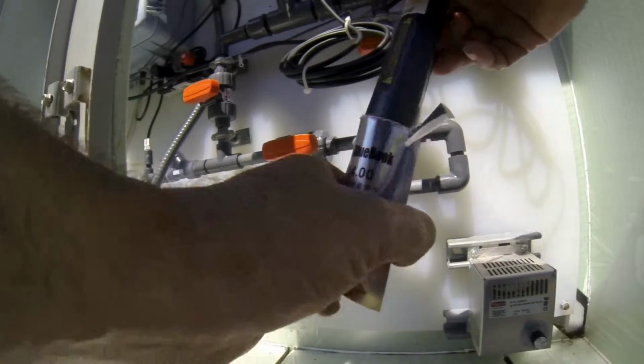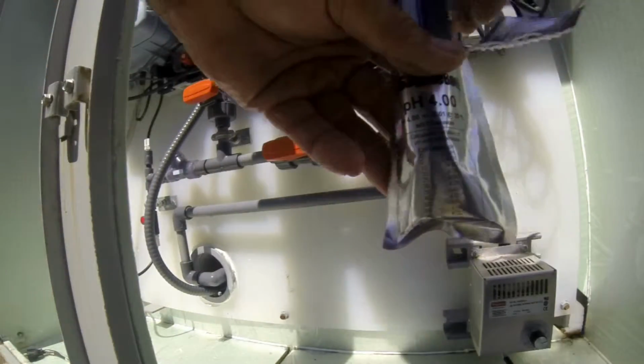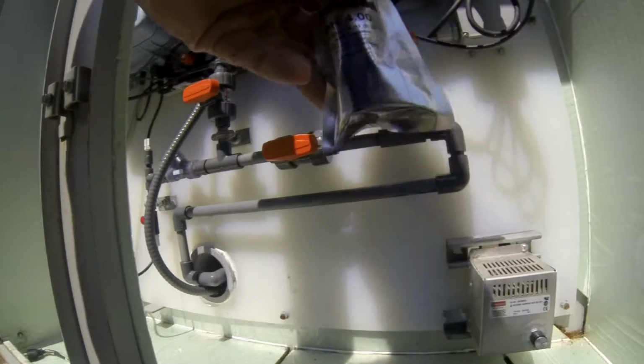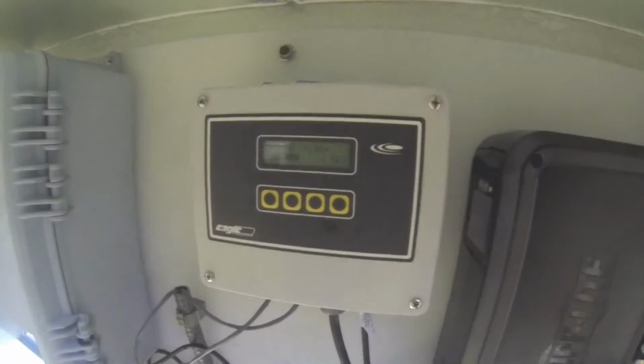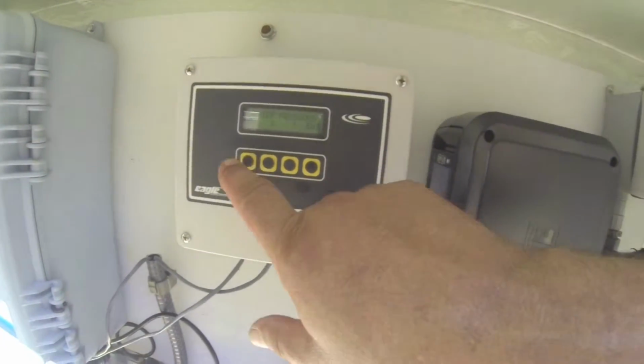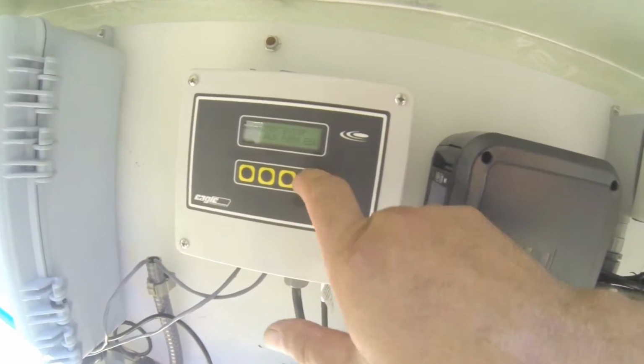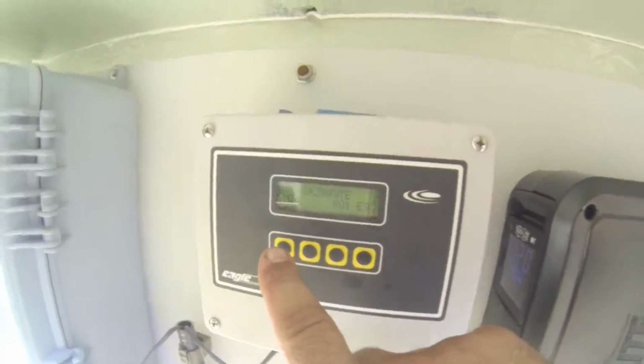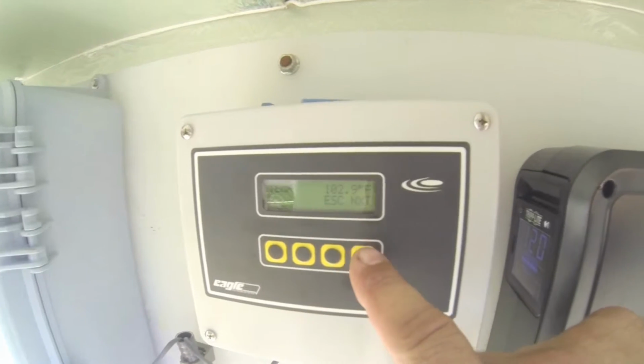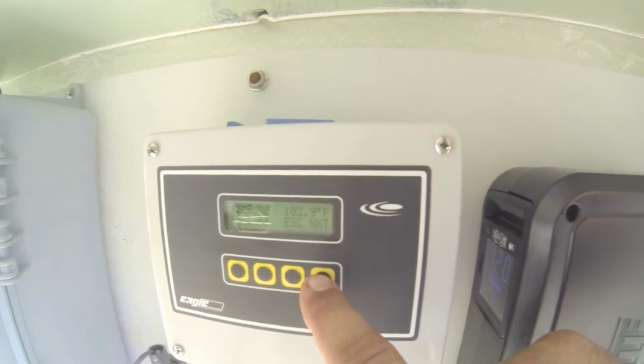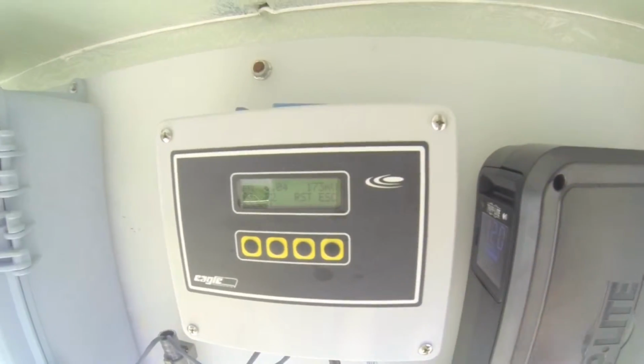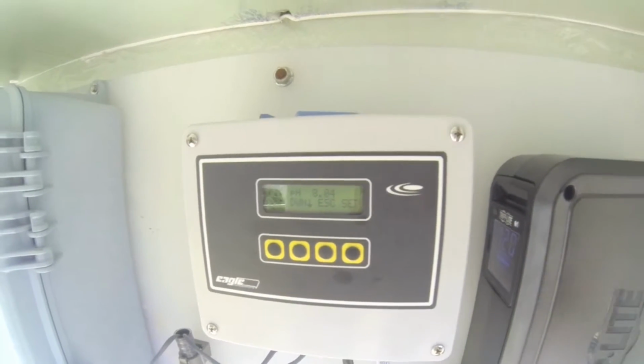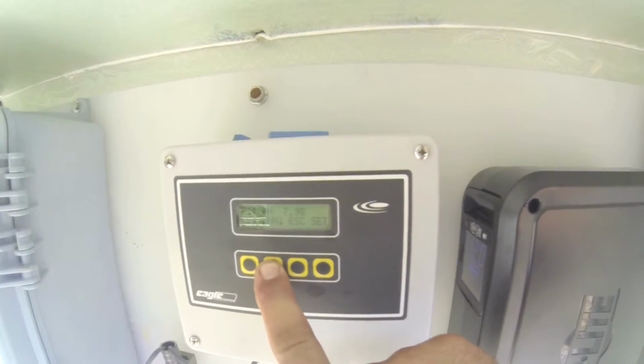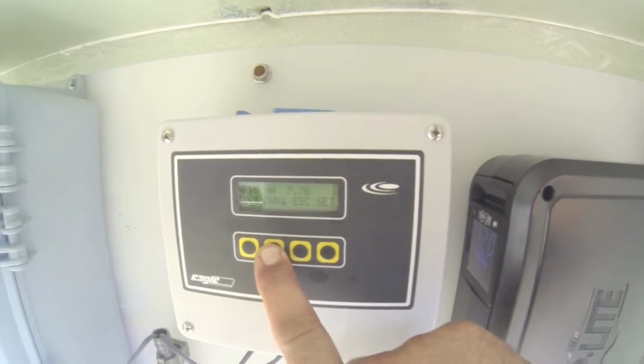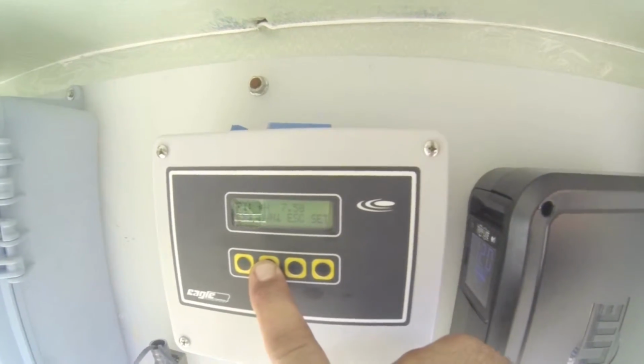We're going to go ahead and place that probe in the buffer 4.00. So we have it in the 4 buffer. Right now we're reading 8. So we want to put in our password, hit enter, calibrate. We're going to calibrate the pH. We don't want to calibrate the temperature. We want to calibrate next and go to P1. And we want to match that to 4. So we want it to be a 4.00.